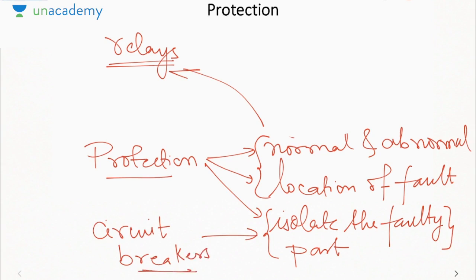Okay. Now, as I told you earlier, since relay has to detect the abnormal condition, it will generally operate at the minimum fault current, because it must be able to identify if the current is greater than the threshold current. Okay.